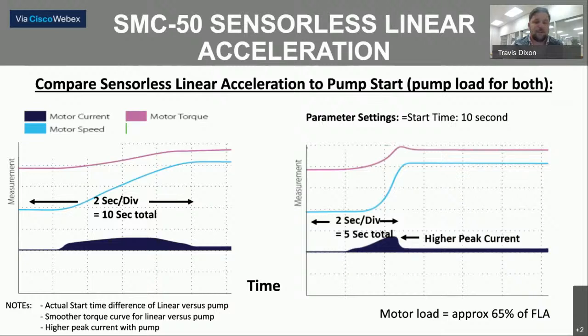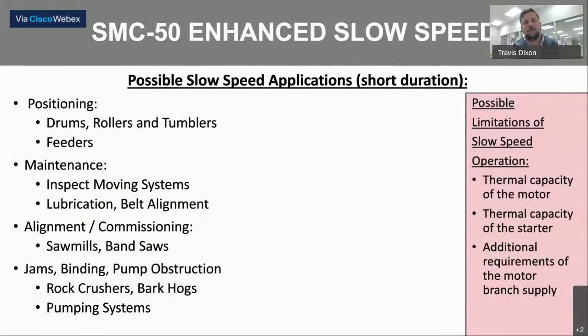Smoother torque than other starting modes, definitely much smoother versus a pump start, as you can see in the diagram. Also, the sensorless linear acceleration will give you the closest start time to what's programmed versus all other methods. Next is the enhanced slow speed, which is also another patented mode. It's also programmable in 1% increments. You can do the slow speed in forward and reverse without a reversing contactor. It's one of the shining points of the SMC 50 because it has very good slow speed torque, unlike competitors or even the SMC Flex.